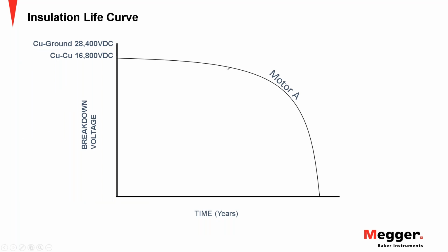So in static testing, even in dynamic, we covered this curve. This is the insulation life curve. If we care about when our motors are going to fail, when we consider that from an electrical standpoint, it's the breakdown voltage of the insulation that we have to consider. And we know that the breakdown voltage at the beginning of life starts at a very high value.